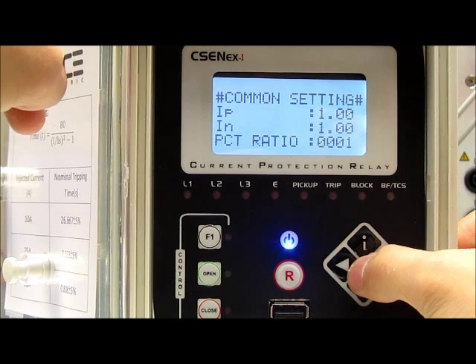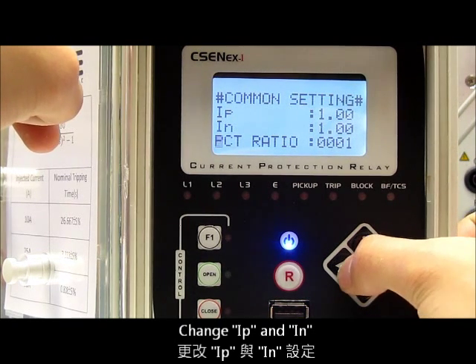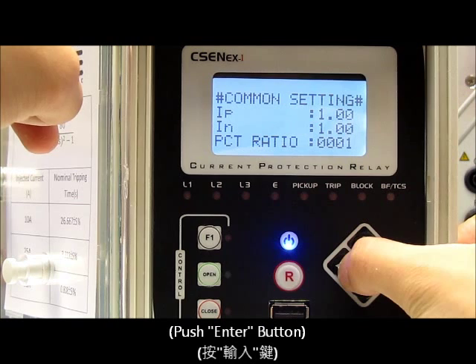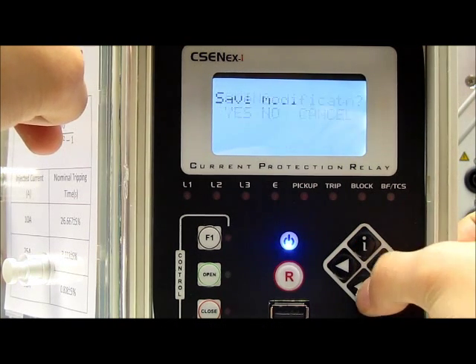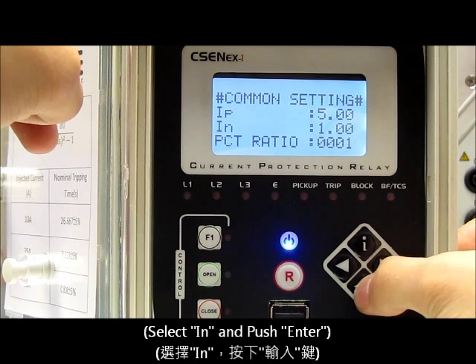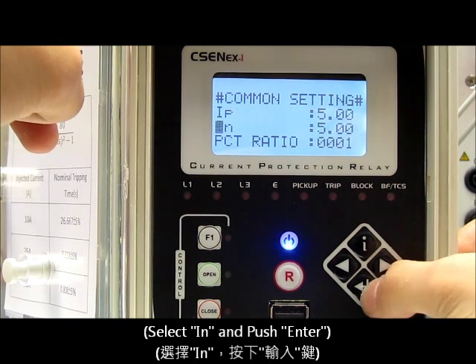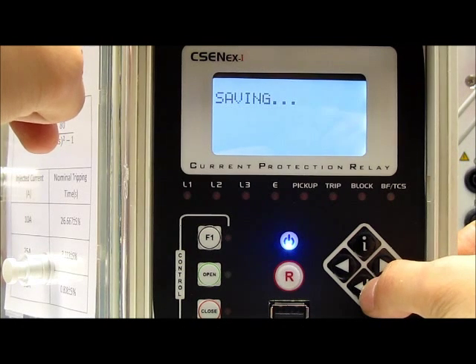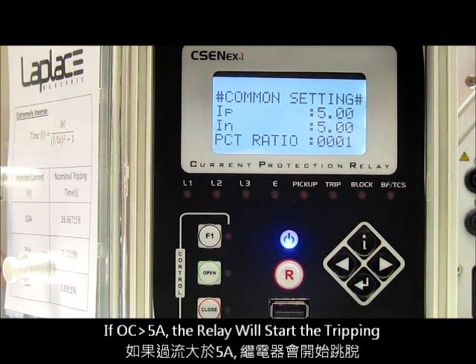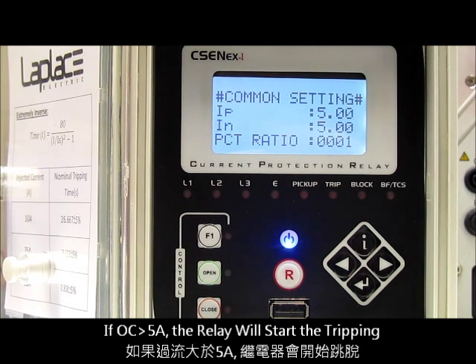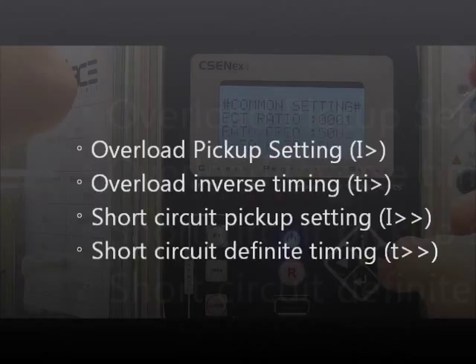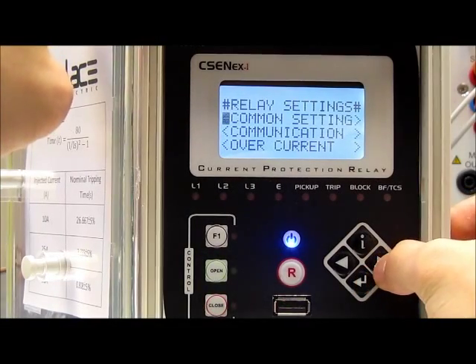Then we change the IP and IN — do it the same way. Push the enter button, change to 5 amperes, and confirm. In this setting, it means that when the current is over 5 amperes, the protection relay will start tripping.